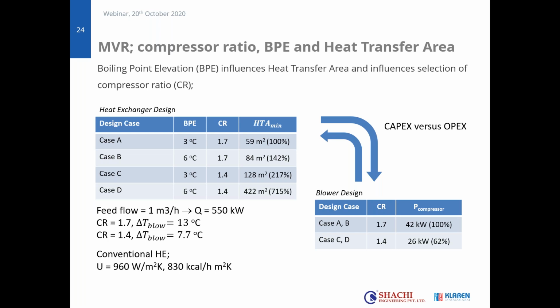We can also do the same for a heat exchanger with self-cleaning, and that will also be later in the MVR Calculator that we will supply via our website. But in this case, I just take a conventional heat exchanger, and a heat transfer coefficient of close to 1000 watt per square meter Kelvin, or 830 kilocalorie per hour per square meter Kelvin. So it's a typical case, and you can change the numbers, but it's important to understand the effect. And you can see the effect in the values between brackets for the heat transfer area.